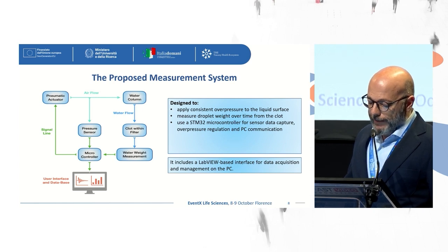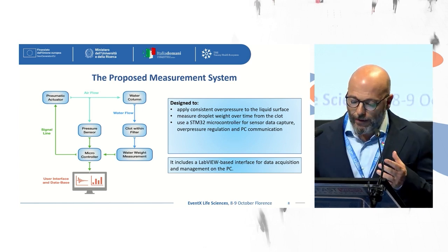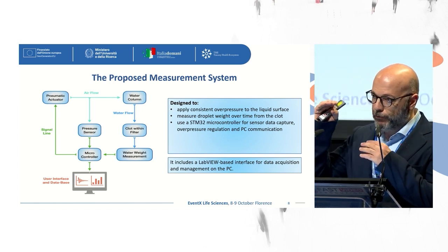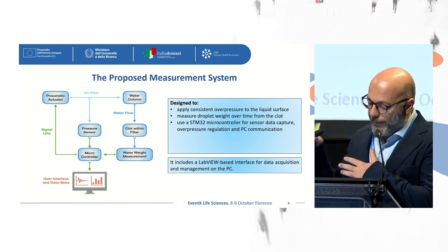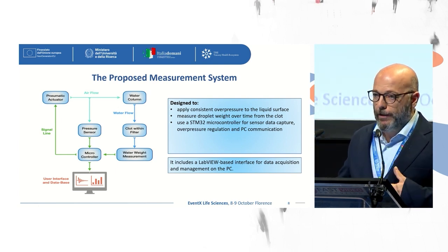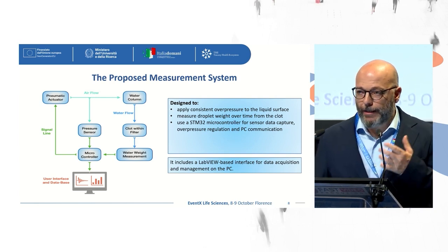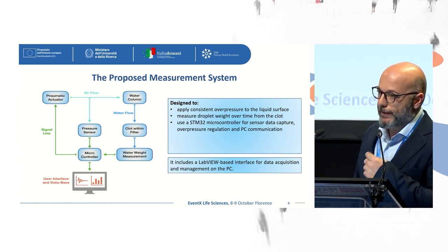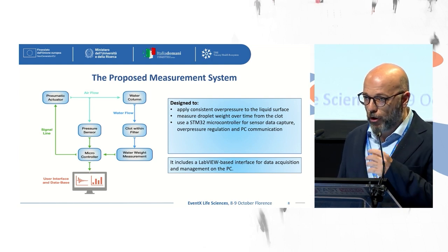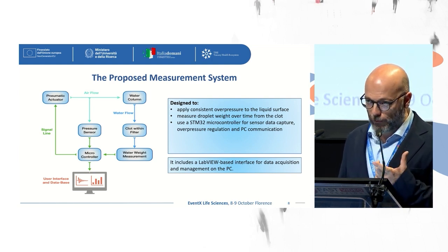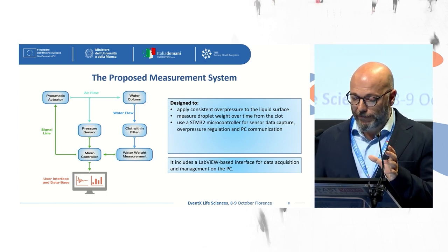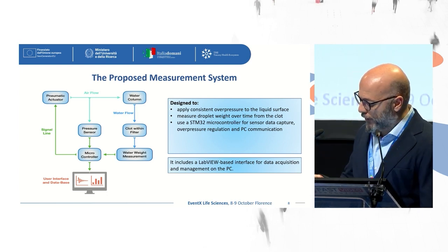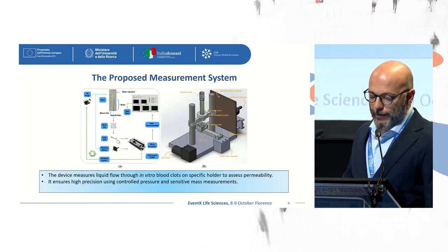Our device is designed to apply consistent overpressure to the liquid surface and measure droplet weight over time from the clot. It uses an STM32 microcontroller for sensor data acquisition, overpressure regulation, and PC communication, and it includes a LabVIEW-based interface for data acquisition and analysis.